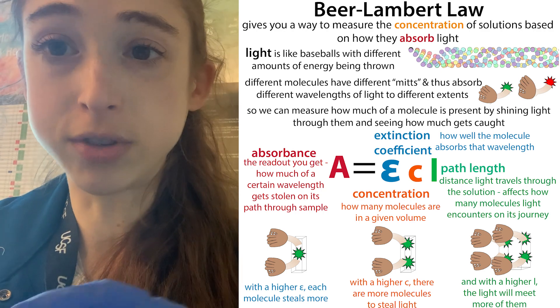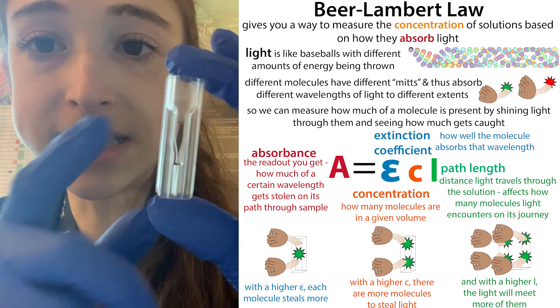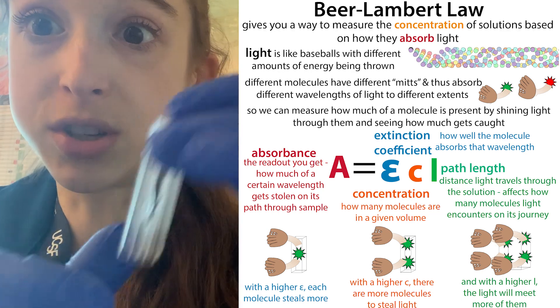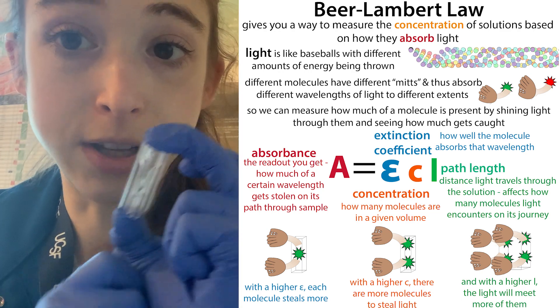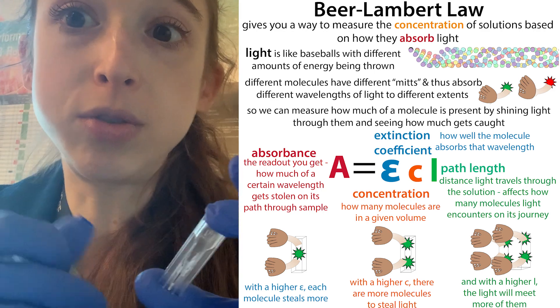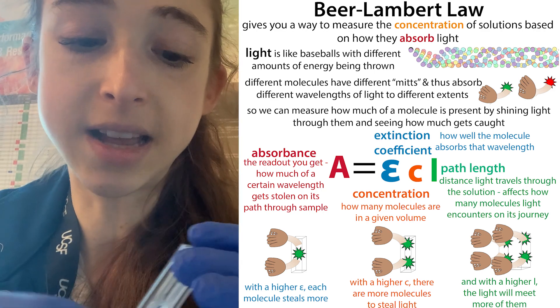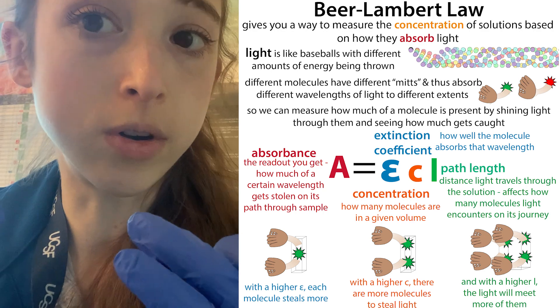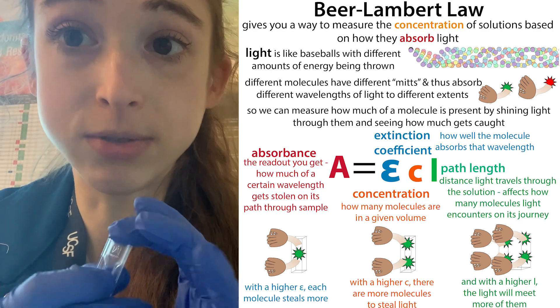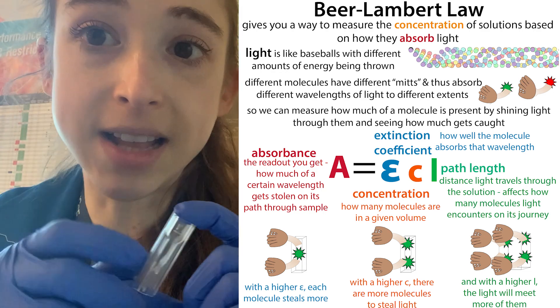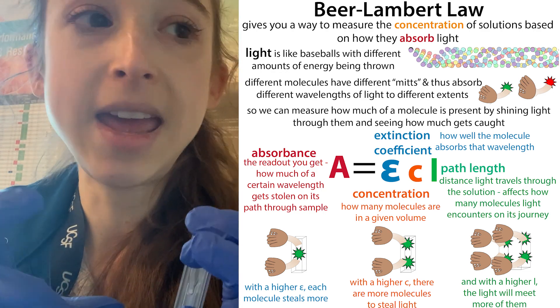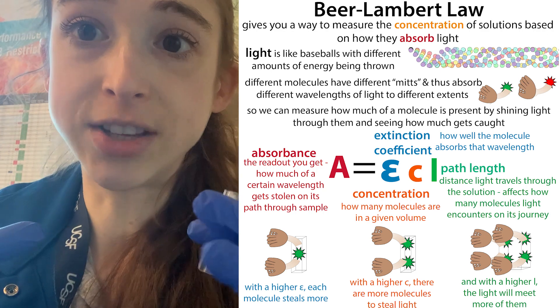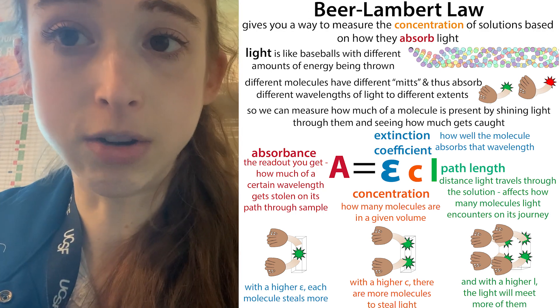In a traditional spectrophotometer, you use something like a cuvette, where you make a column of liquid and the light shines through that column. You fill your tube with liquid and you typically need a lot. The absorbance depends on your path length, your extinction coefficient, and how many molecules are in there stealing that light. The more molecules there are, the higher the absorbance gets. With a fixed path length like a cuvette, if your sample is too concentrated it will oversaturate the detector and you won't get an accurate reading.